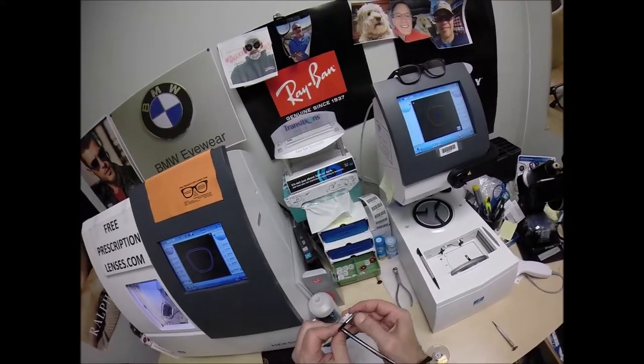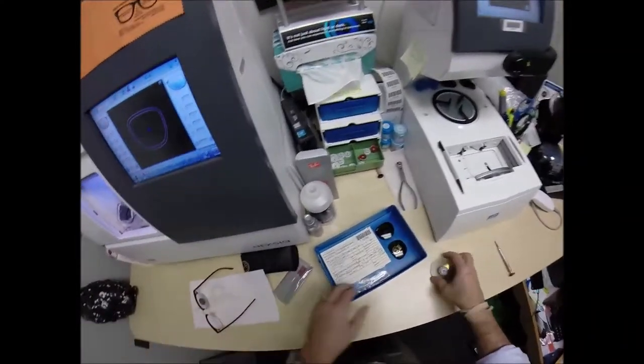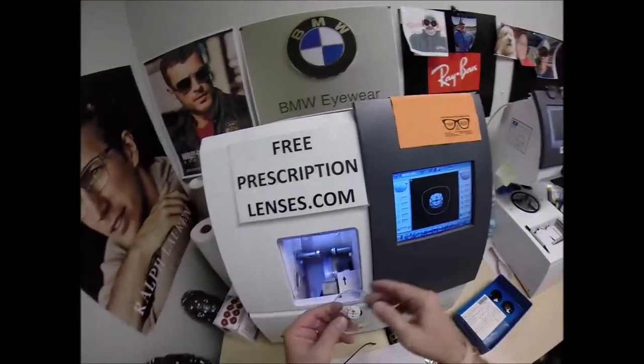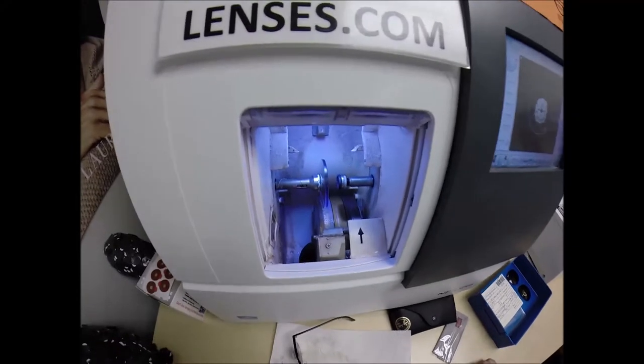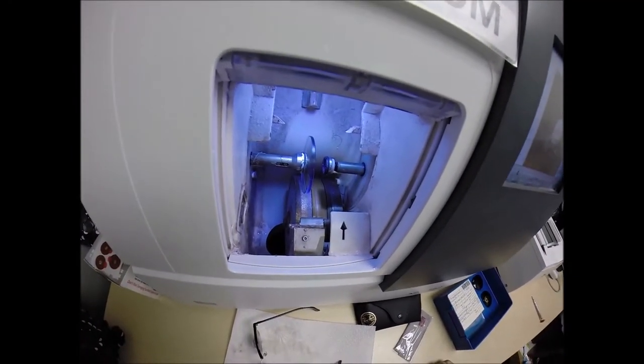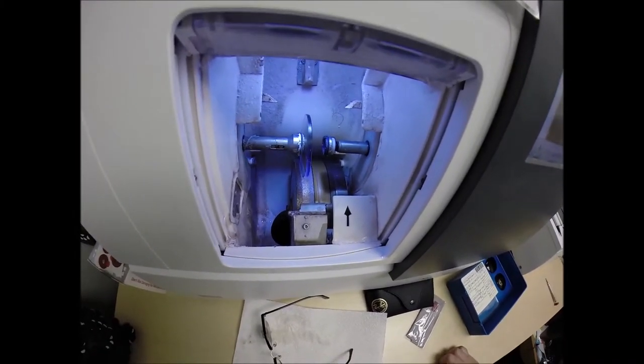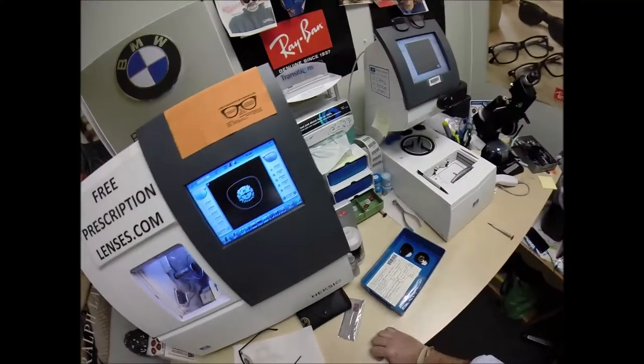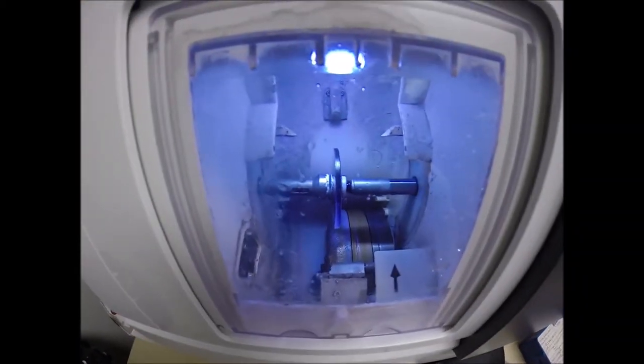And we are good. That is in there. I see a little more optical sawdust I can clean off with my thumbnail though. So let's go ahead and start cutting the left lens. We're going to flip that over to L, place the magnet into the Chuck. Hit the start button. The door closes. The clamp shuts. The lens is going to be traced again by the two white styluses, this time tracing the left side. And you can see as it's going around tracing that shape. And just like before, measuring the thickness of the lens to automatically place the bevel so you have the least amount of edge thickness showing. Look at that, David. You got nothing. You got nothing there.